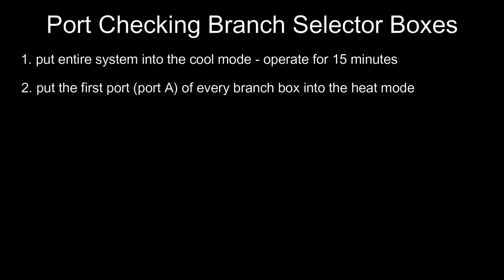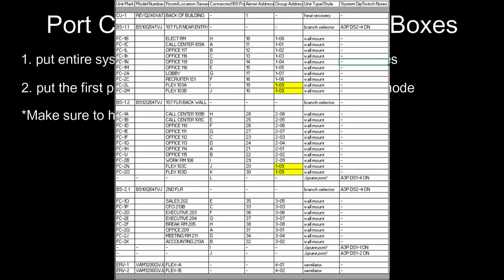The other thing to keep in mind is that an as-built is an absolute must for this part of the operation. You need to know which units are wired to which boxes and ports. It's very, very rare that an indoor unit gets wired to a completely different box compared to what the as-built would say. It happens, but it's rare. Most of the time, the issues that arise are that two or more indoor units on a single branch box get wired to the incorrect ports, and we'll find out what this looks like shortly.